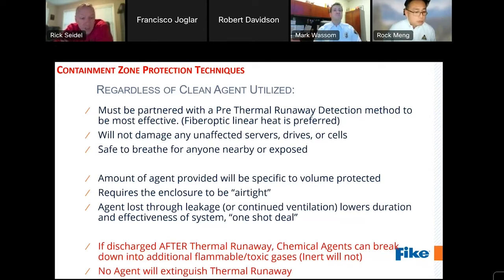And again, if it's discharged after thermal runaway, the other item to keep in mind is that chemical agents can break down into additional flammable and/or toxic gases at very high temperatures that are very easily achieved in a thermal runaway event of lithium-ion batteries, whereas inert gas systems will not. No agent will extinguish thermal runaway, another key item to keep in mind that we can't stress enough as we're going through this presentation. Next slide, please.